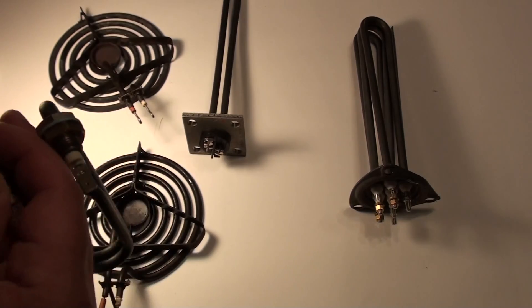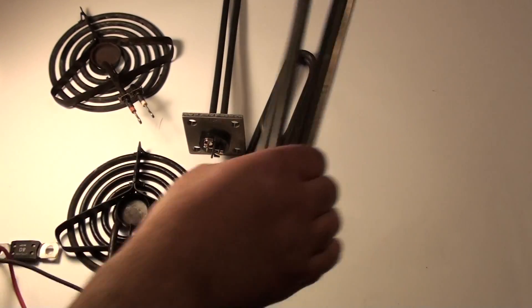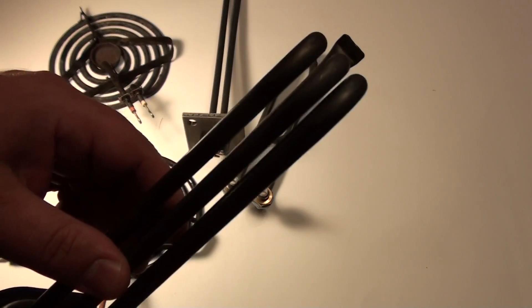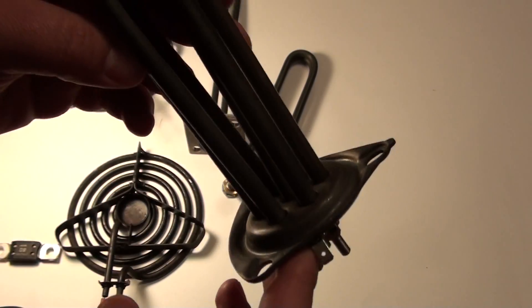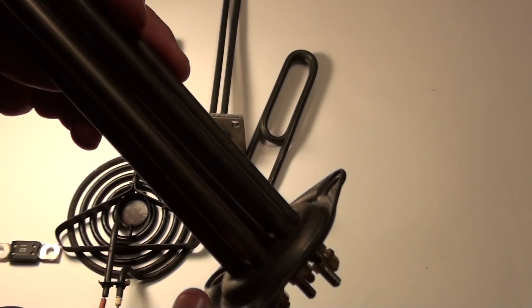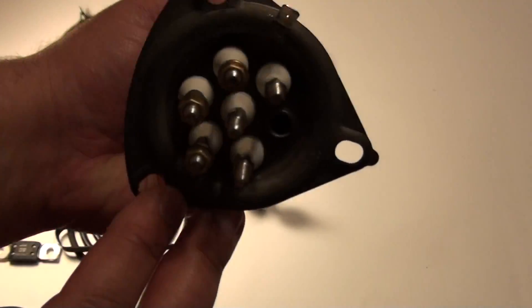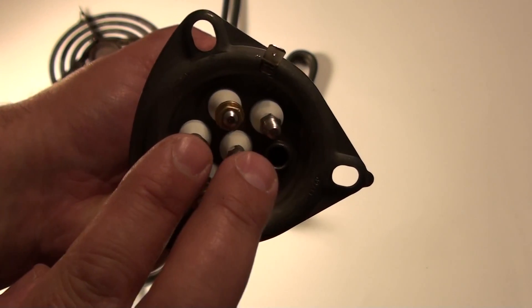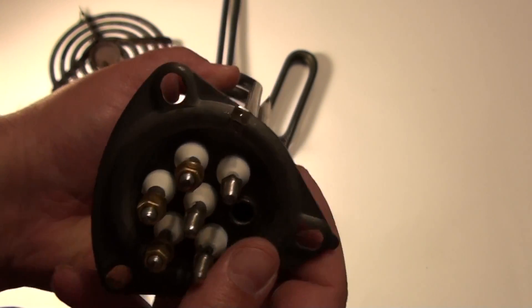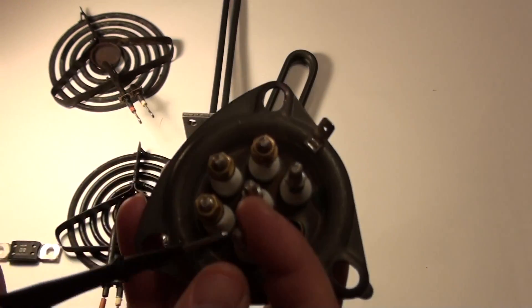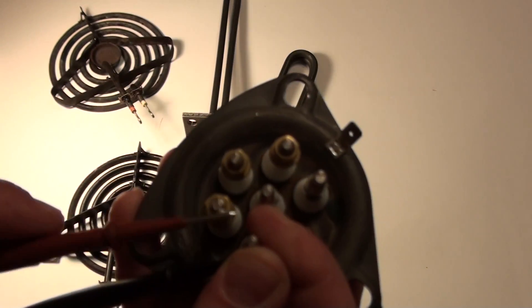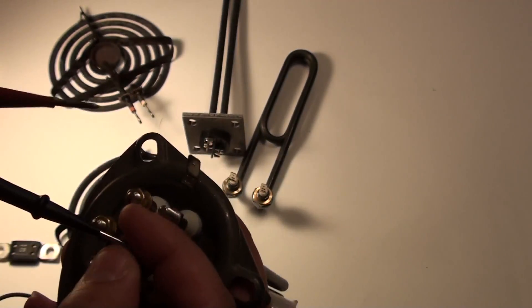And I got this element, it's a bit different. It has three elements at the same time. I don't know if you can see it properly, and it's got these are the connections: first element, second, third. So we're gonna check the one in the bottom here. It's working. The one in the middle, and the last one.